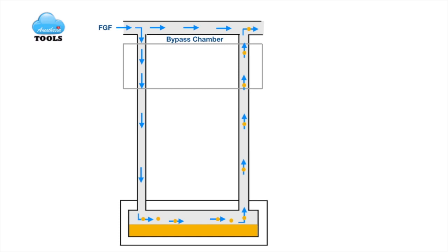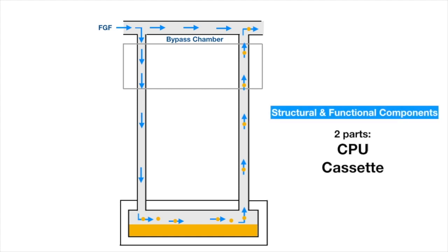Now you are thinking: what's special about the Aladdin vaporizer? How does it give precision output and the safety features it's known for? No worries — the answer follows. Let us see the structural and functional components of the Aladdin vaporizer. Two parts: one, the central processing unit (CPU); and two, the agent-specific vaporizer chamber or cassette.